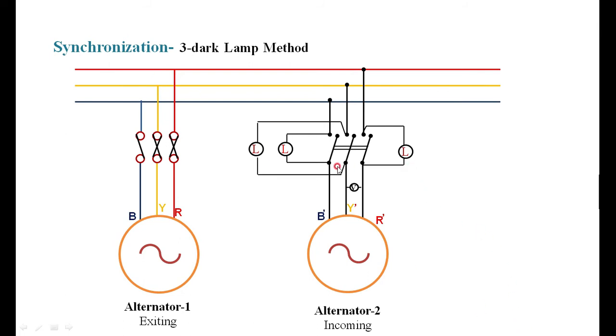Instead, if the lamps go dark and bright sequentially — one by one, cyclically blinking in sequence — then the phase sequence of the incoming machine is not the same. In that case, you have to interchange any two phases and once again observe the lamps. If they are going dark and bright simultaneously, you can conclude that the phase sequence of the incoming machine now matches the bus bar phase sequence.